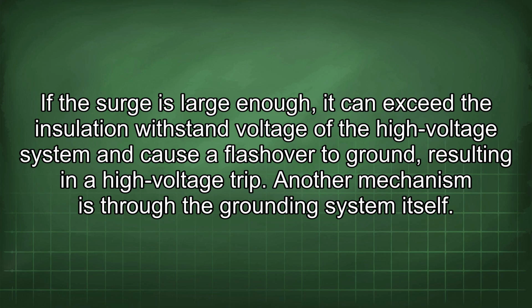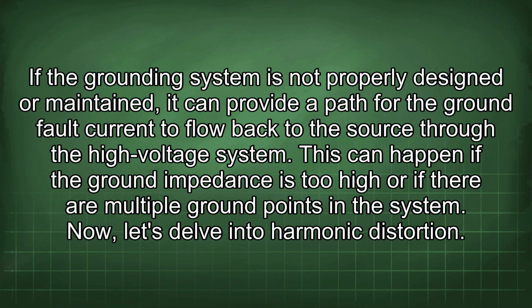Another mechanism is through the grounding system itself. If the grounding system is not properly designed or maintained, it can provide a path for the ground fault current to flow back to the source through the high voltage system. This can happen if the ground impedance is too high or if there are multiple ground points in the system.